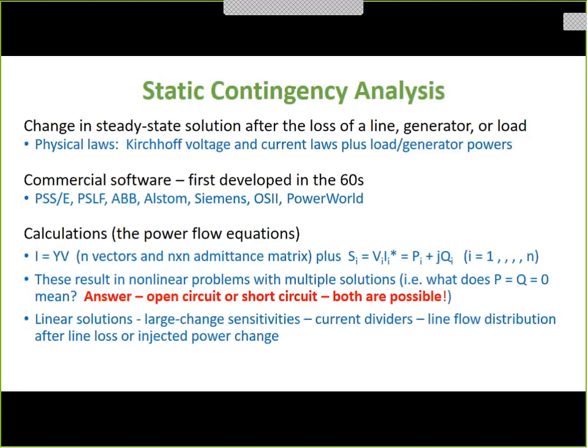The linear solution that we use, if everybody's heard of large change sensitivities, large change means you open up a line. That's not some little epsilon perturbation. You open up a line, that's a big change. But those of you that have had some circuits know that there's a thing called large change sensitivities. Others that have had circuits will say, oh, that's just a current divider. You open up a line, that current has to go somewhere. It's going to go to parallel paths, paths of least resistance or impedance. So that idea of large change sensitivities is really valuable for us because we can do loss of a line and see how it redistributes. And we can use linear algebra for that, not the nonlinear full-blown load flow. Now, it's not quite exactly right, but it's okay. It's really quick.